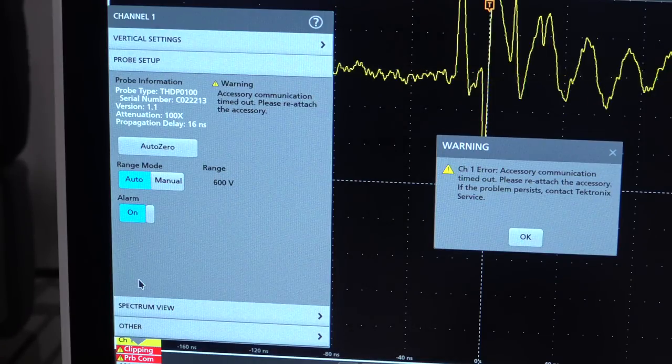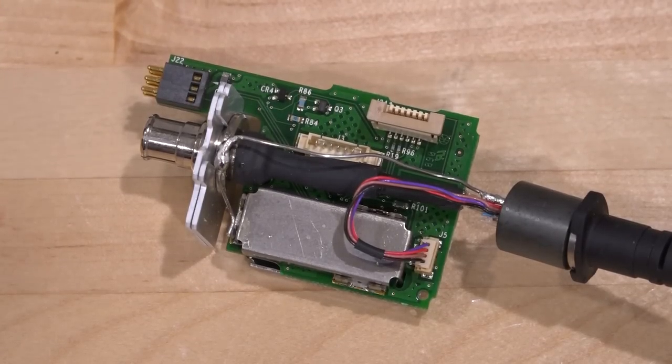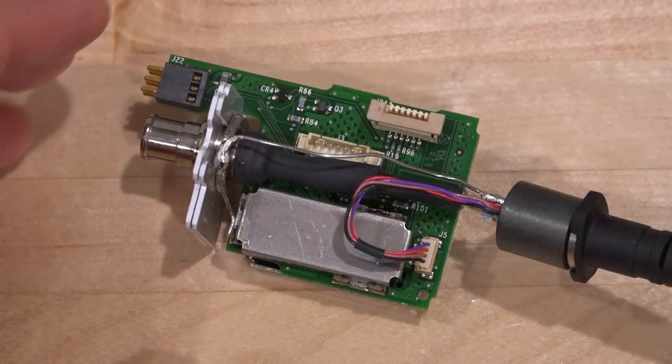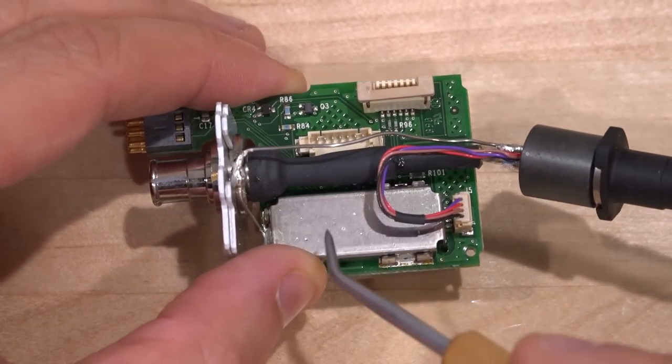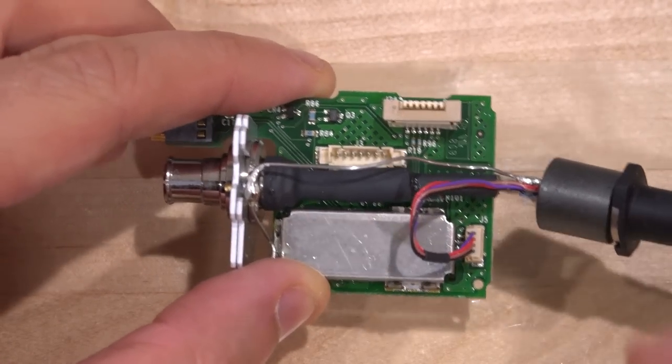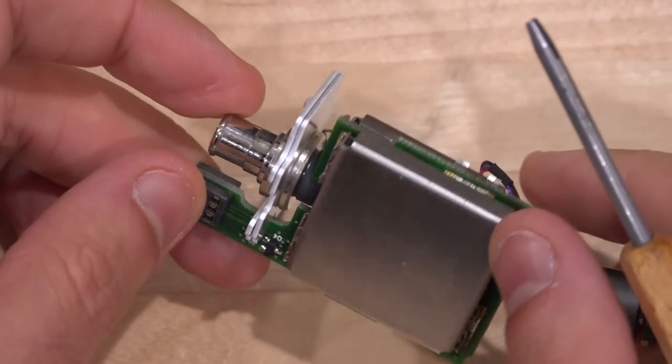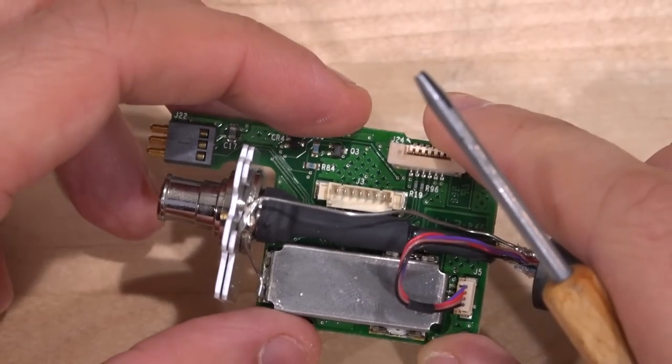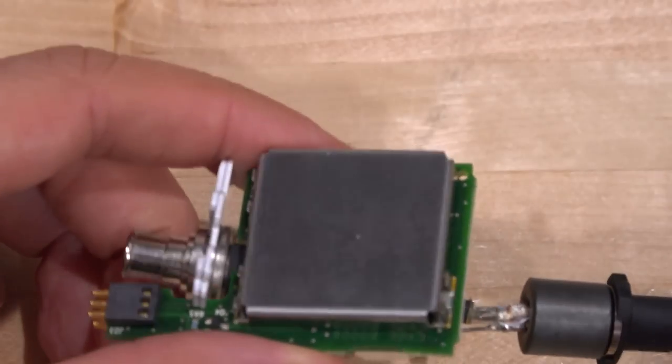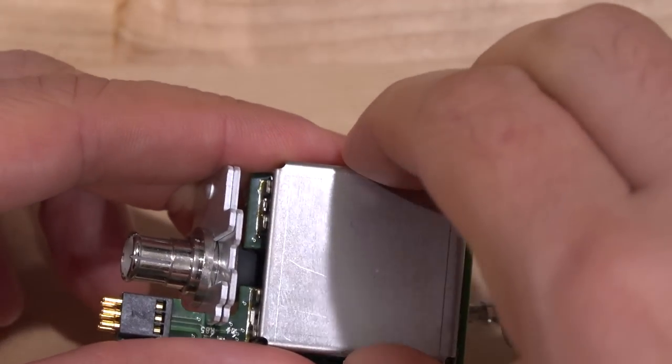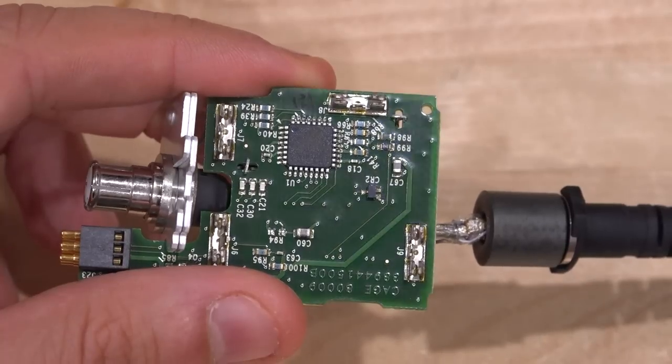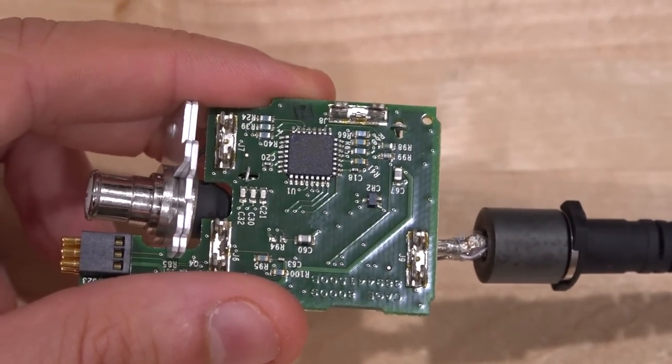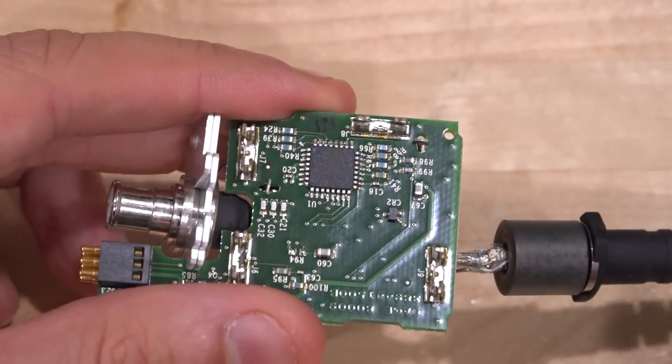Let's take a look at it. Here's the front end of the probe. This doesn't do any of the high voltage magic, that's all done in the other part of the probe. The interface to that is the RF interface and a couple of wires here for providing power and some communication. There are two metal shields protecting everything here. Here are the pogo pins that interface directly to the front of the instrument. There's our microprocessor there that's going to do all the communication.